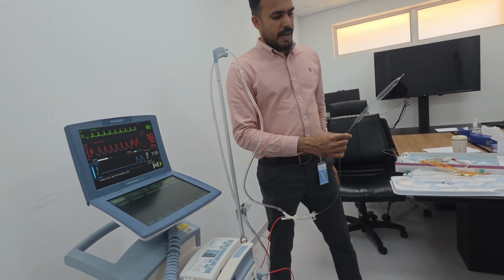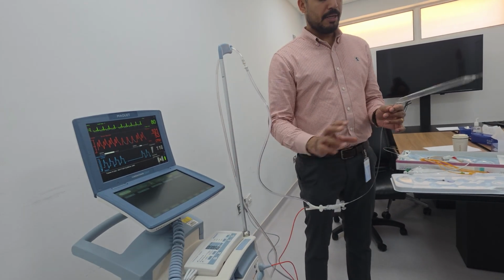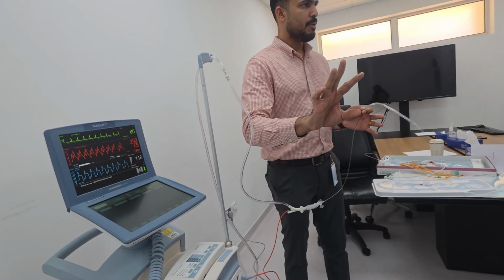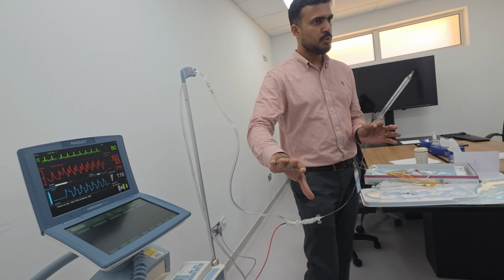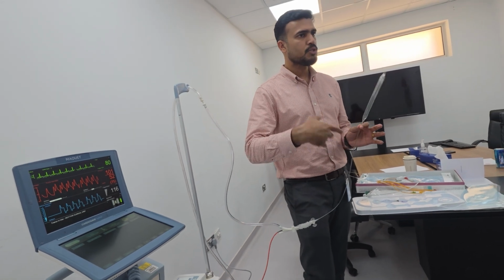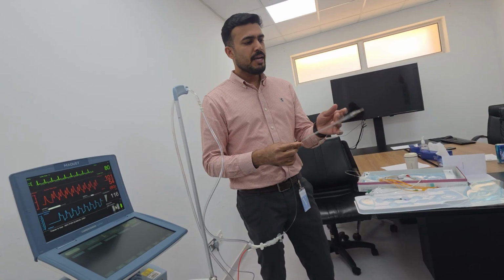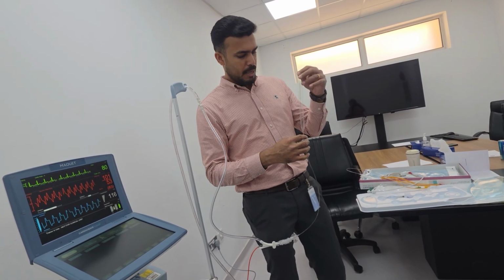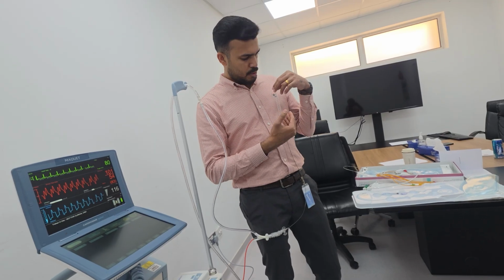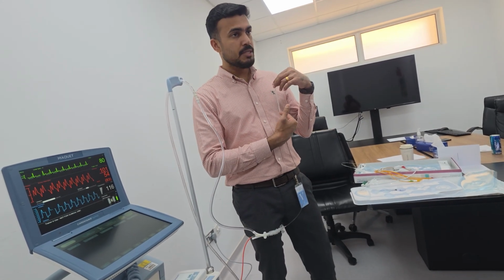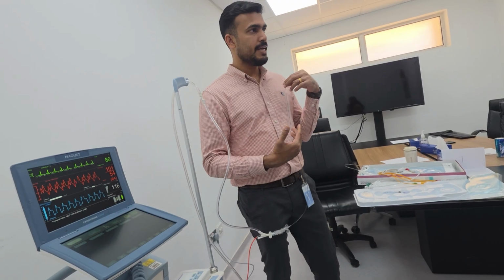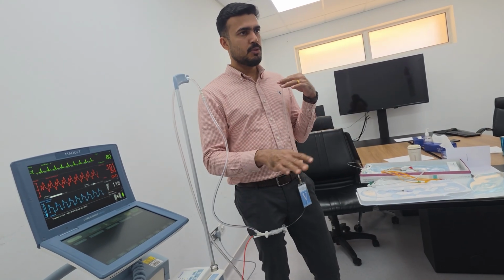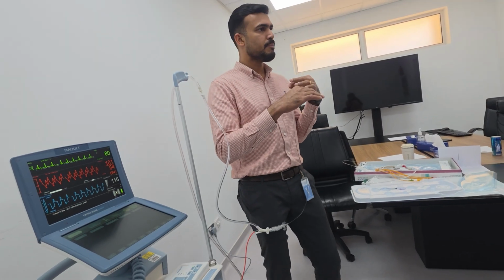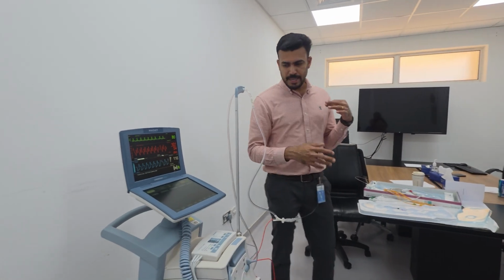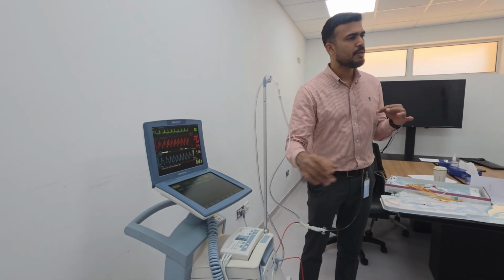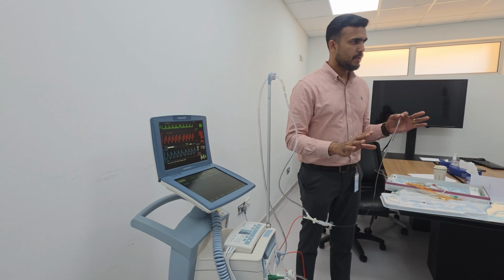And again, the third option for this IABP button. So you are getting a gas loss alarm continuously from a patient. You are doing a proper manual autofill, proper troubleshooting. There is no leakage, but around every 40 minutes or 1 hour you are getting the alarm continuously. Then it is a leakage, but it is not an actual leakage. Maybe the patient's temperature is a little bit high. If there is a temperature difference, the gas can diffuse through the membrane. Okay, so that's not a leakage. You should confirm that you have done proper troubleshooting, there is no leakage, and this is happening only because the patient has a high temperature. In that case, do not wait for the 2 hour autofill. In 1 hour you can do a manual autofill just to compensate. Okay, only in that case.